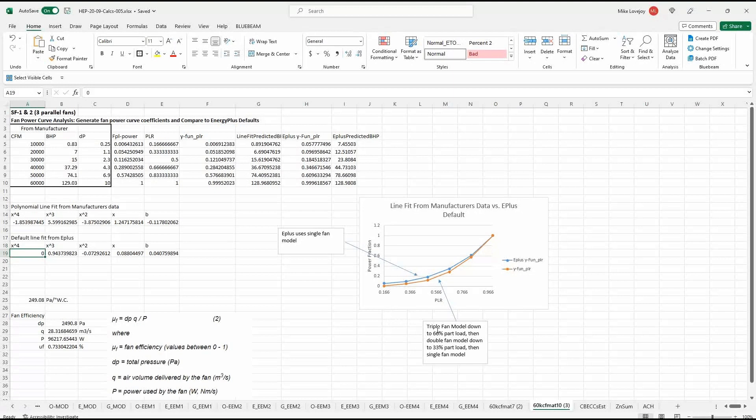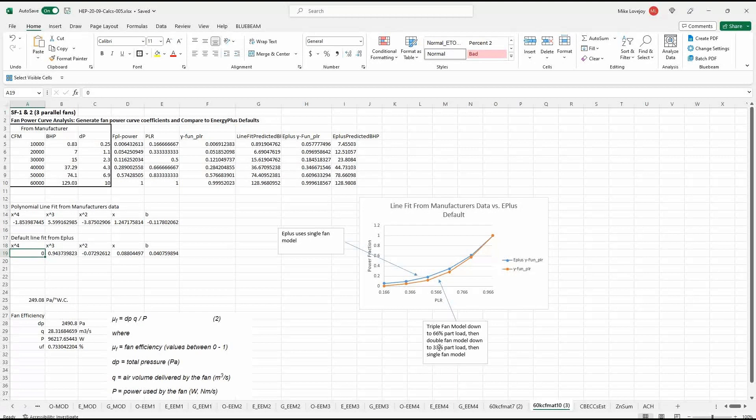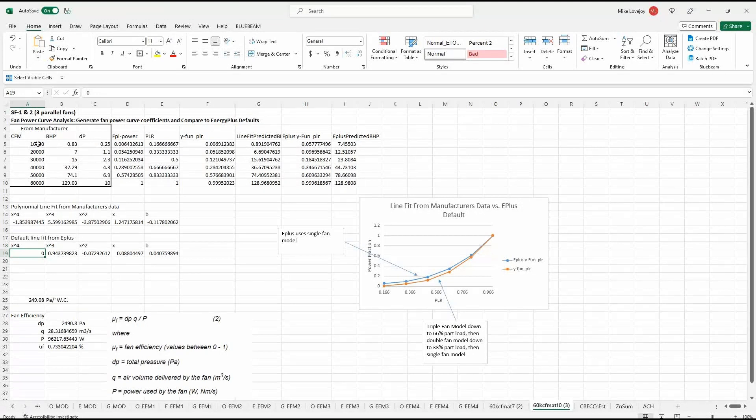So this is a triple fan model and from 100% full load all the way down to 66% part load that has all three fans running. And then we have a double fan two fans running down to 33% and then a single fan down to the minimum flow which in this case is 10,000 CFM.